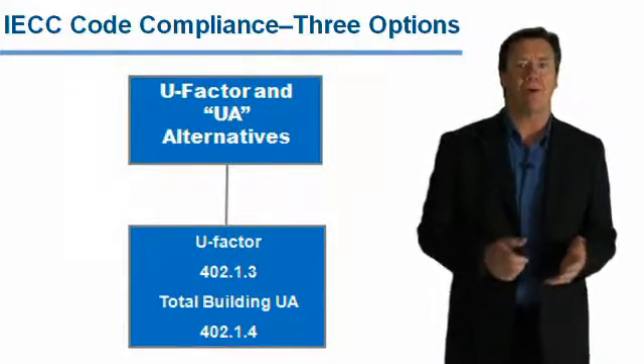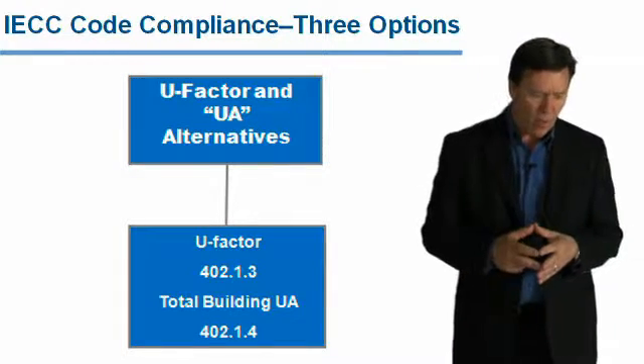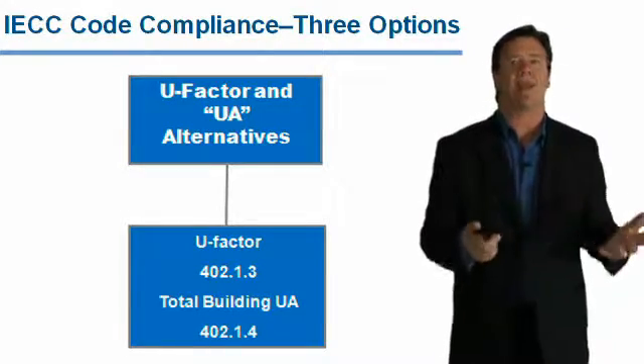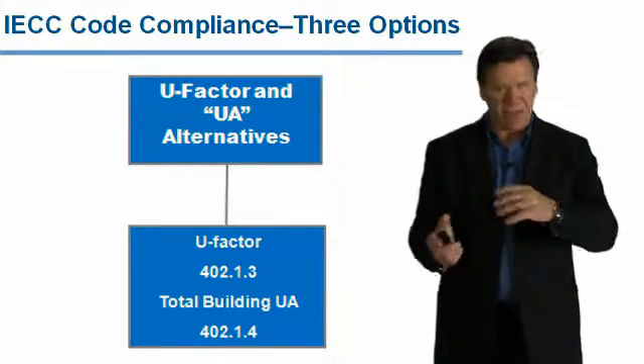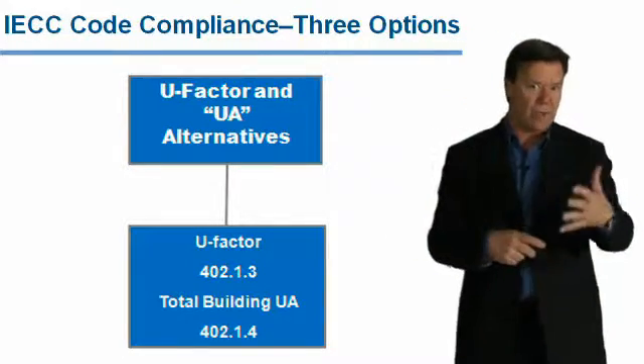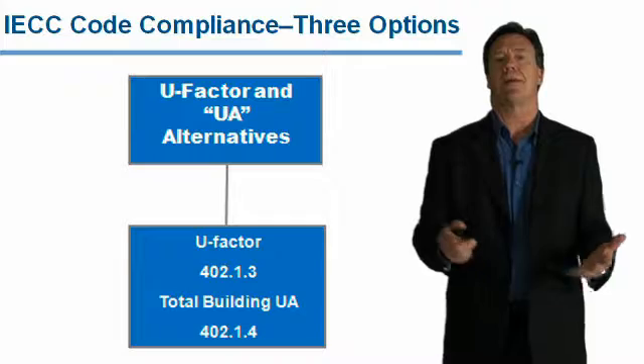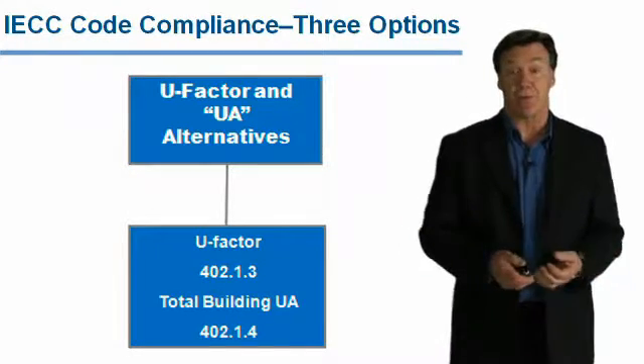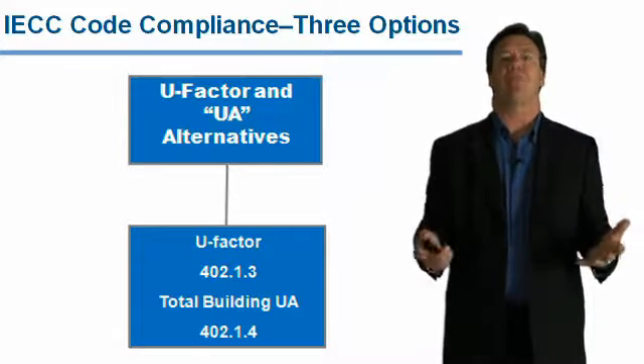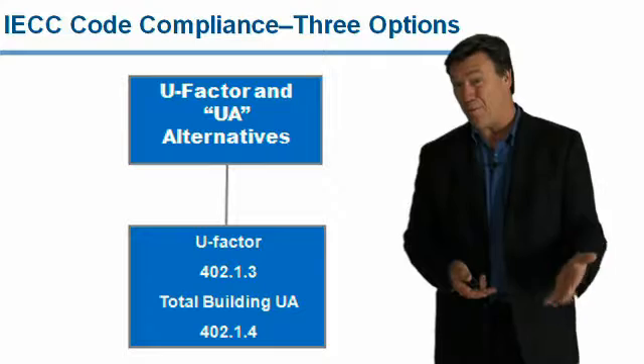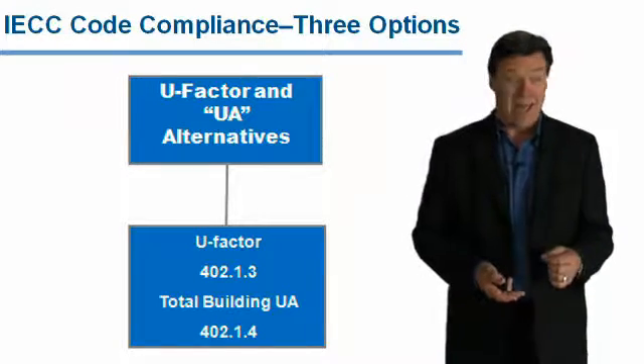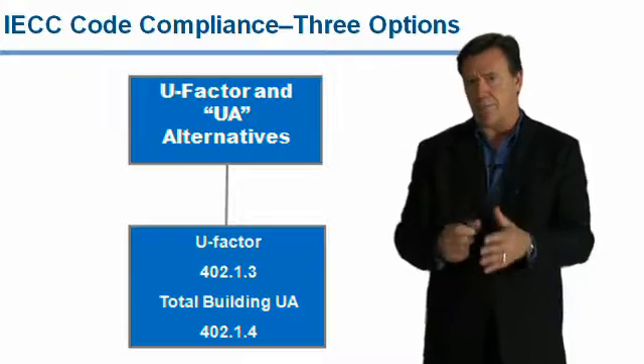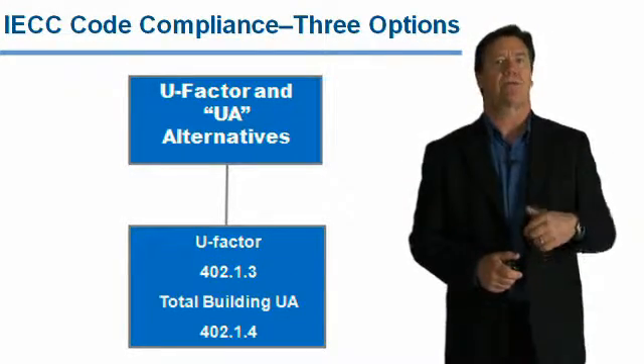The second method is what we call a U-factor or UA alternative. These are used in two basic areas. One is, for example, we're using SIPs panels or log homes or maybe advanced framing, where the R-value of the material is really different than a conventional framed wall. This allows us to take the U-factor into account because, for example, when you look at a typical framed wall, framing accounts for about 20% to 25% of its surface area. So if you have 25% framing, that means in 1,000 feet of wall that's at R19, really about 250 feet of that wall is at about R4.35, which is the R-value of a stud, and 75% is at R13.